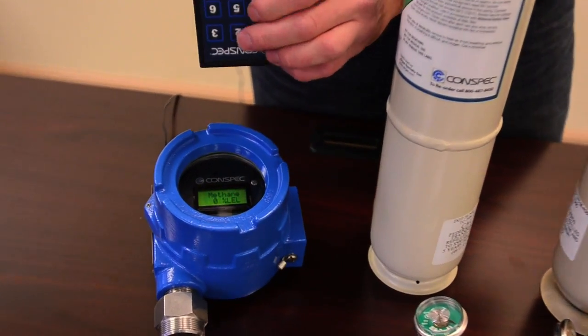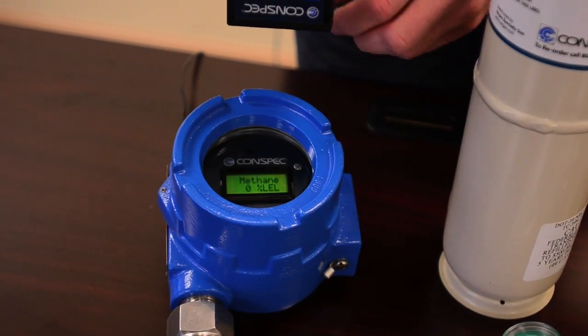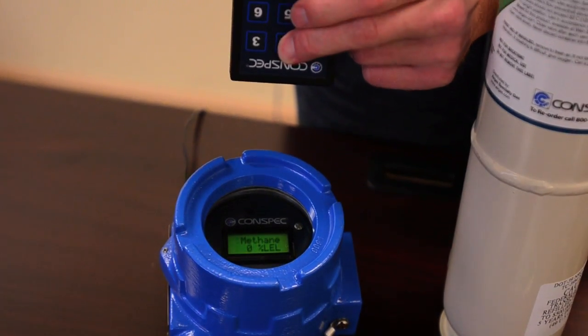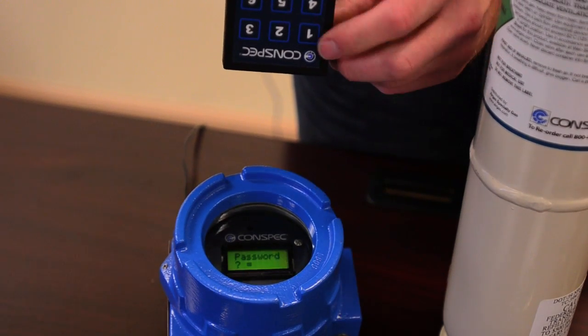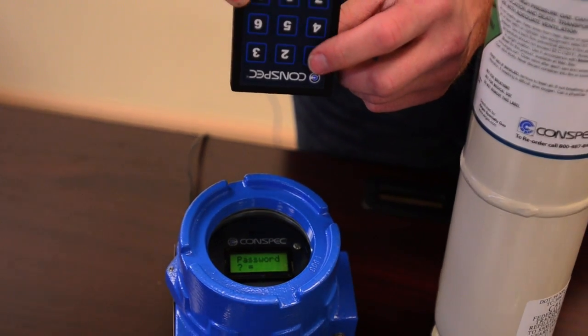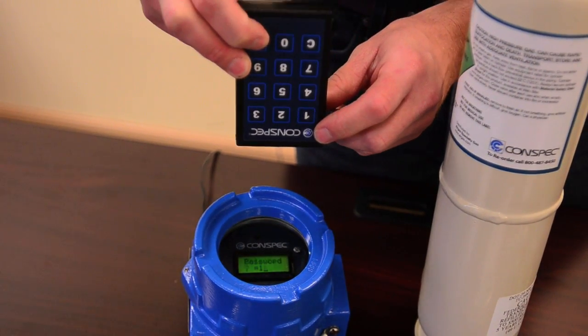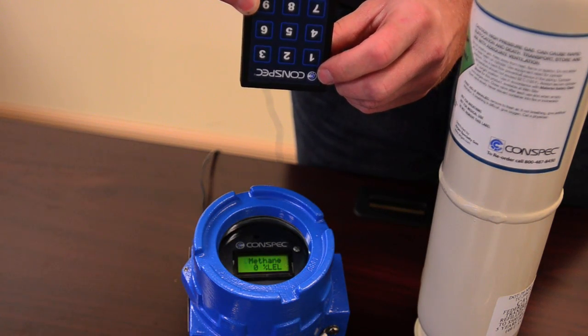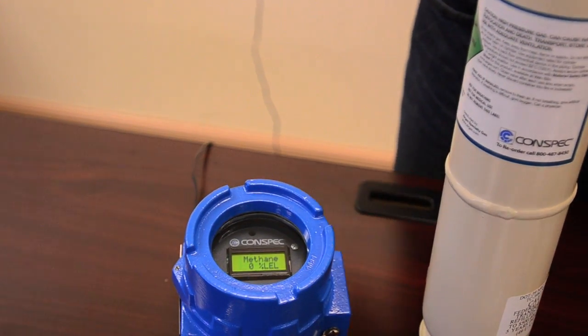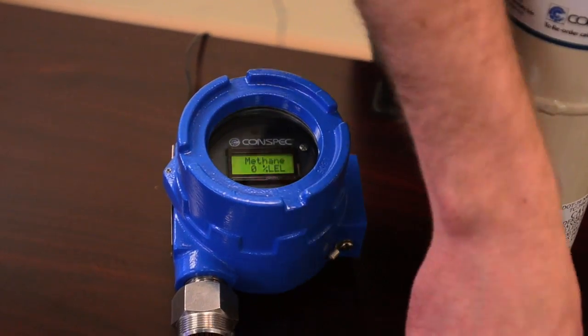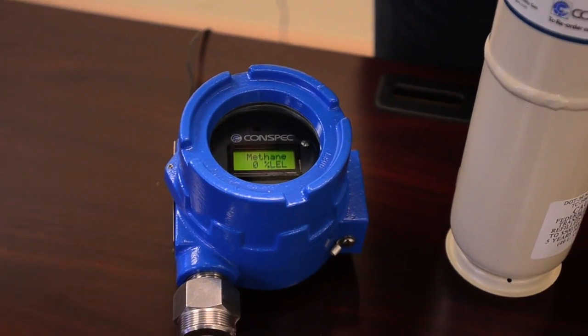We do this by entering the function 25, enter, and the monitor will ask you for the password. Default is set to 1, enter. Now the monitor is unlocked, so we can begin connecting our calibration fittings to prepare for the calibration.